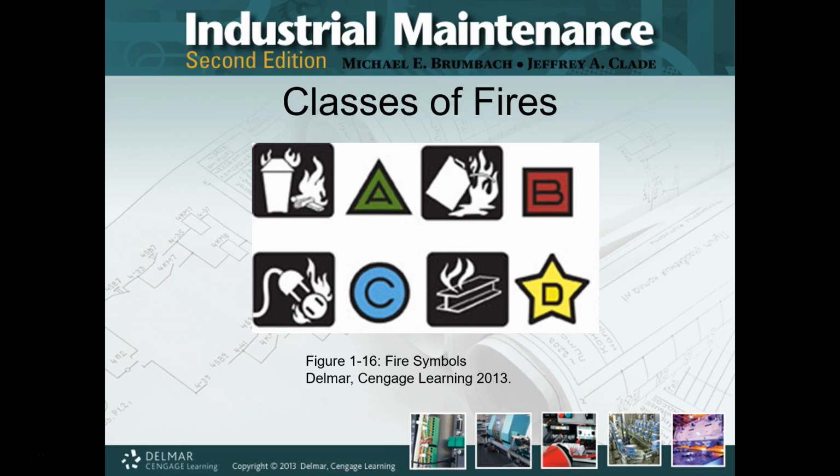All right. Now the good news is most of the time for kitchens, they typically have their own little area and their own little extinguisher that's going to be directly over the grills that it is associated with. And I highly encourage you to use the extinguisher station for that area because it'll also shut down the exhaust fan.